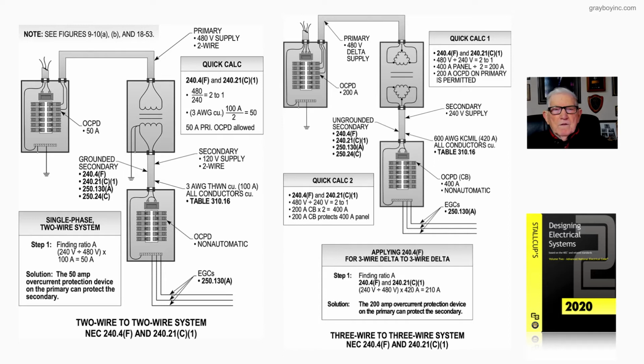But now, remember this is single phase we're looking at. Now for 3-phase, the quick calc would be the same. The tap conductors for secondary transformer conductors would be the same. So quick calcs 1 and 2 would be basically the same that we would be reviewing there. But now to determine what size conductors we would use here, notice we're using 600 kcmils, good for 420. All conductors are copper, selected from table 310.16, and we're selecting those from the 75-degree column because we're not derating in any way.